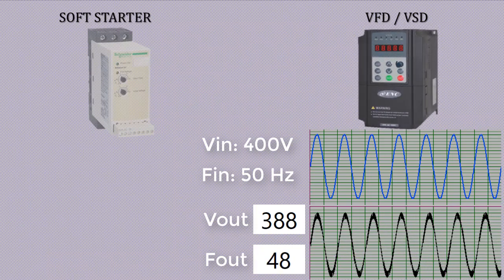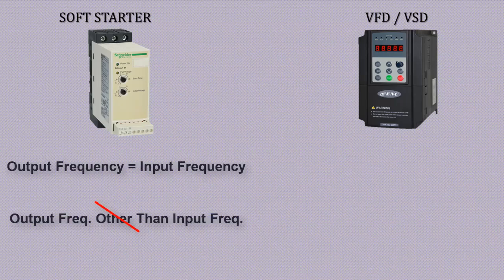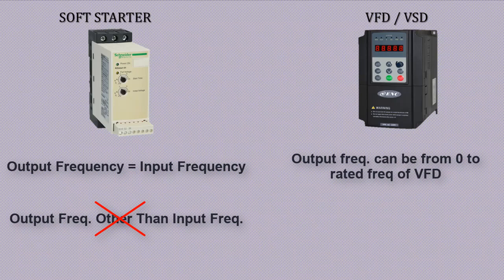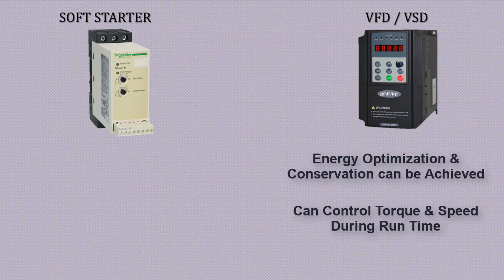Soft starter can't provide intermediate speed other than rated, while using VFD you can get any speed from 0 to rated speed and also controlled torque. VFD can optimize energy usage by matching motor speed to load. Soft starters do not provide this benefit.